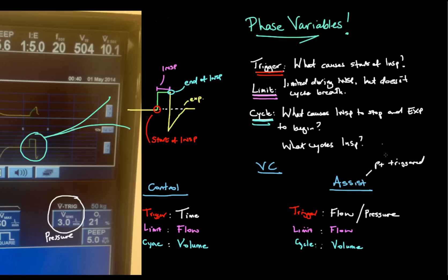In this video we looked at trigger variables — what triggers the breath to start — limit variables — what's limited during the breath but doesn't cause the breath to end — and cycle variables — what causes inspiration to end and expiration to begin. These are called phase variables and they're going to be pretty important when we start to look at all sorts of different modes of mechanical ventilation.